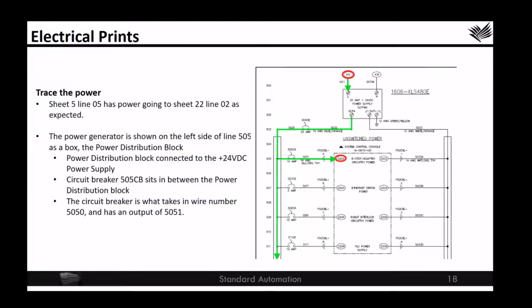So when we go to the PDP drawing package at sheet 5, line 5, we see that that in fact does go to sheet 22, line 2, and is inside of the 121 package that we were looking at earlier. We see that the wire coming to the SAC is actually a 14 gauge wire and is blue with an orange tracer. We also see 505CB device, which is a circuit breaker located on sheet 5, line 5, and we can see that it is a 10 amp circuit breaker. Now this power distribution block is connected to the 24 volt power supply, and we've now effectively traced the 24 volt power supply through the system. The circuit breaker specifically is what takes the wire number from 5050 to 5051. That's supplied to the SAC and eventually to slot 0 of chassis 1.